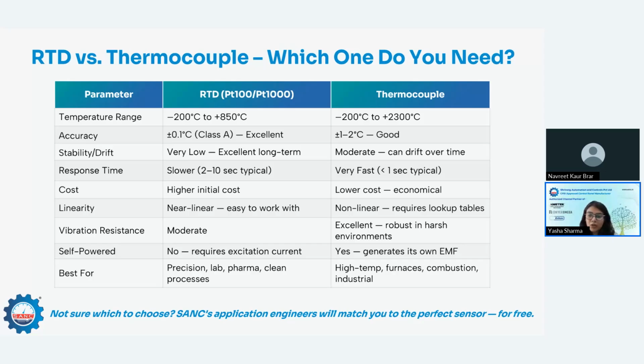Then accuracy. If you want plus or minus 0.1 degree centigrade, like class A accuracy, which is an excellent range, then you should go with RTD. And if you can accept plus or minus 1 to 2 degrees centigrade of good accuracy, then you should go with thermocouple. Then stability and drift. Drift will be very low with RTD when you're talking about long term applications at the lower temperature range, and if you can accept moderate drift, then you can go with thermocouple. For response time, if you want slower, less than 3.5 minimal, or 2 to 10 seconds typical, then you should go with RTD. And if you want very fast response, less than 1 second, then thermocouple.